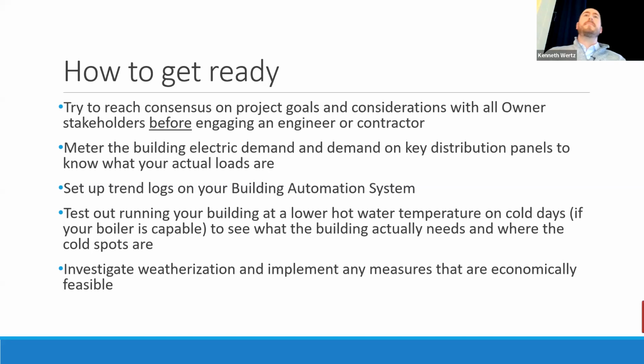Yeah, please. You mentioned earlier that maybe the service size changes. What's your best estimate for a building of 100,000 square feet, after increasing the service by 20% to 30%? Yeah, it's a great question. So the question was, for a typical 100,000 square foot school or typical building, how much would the service size have to go up?